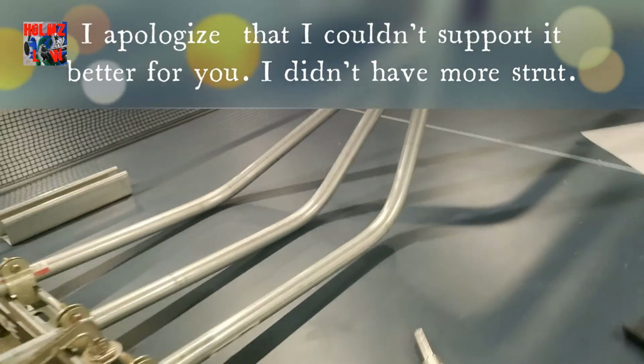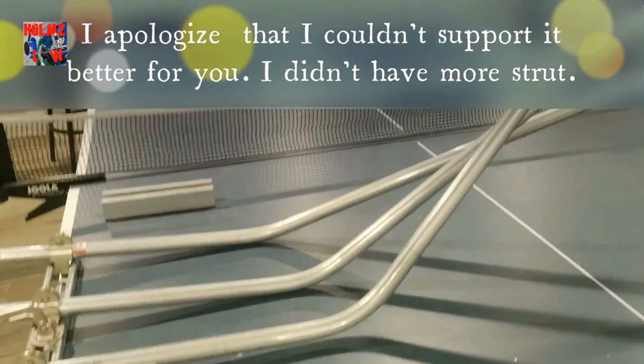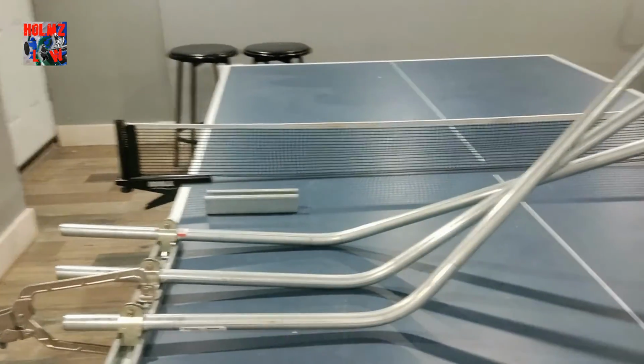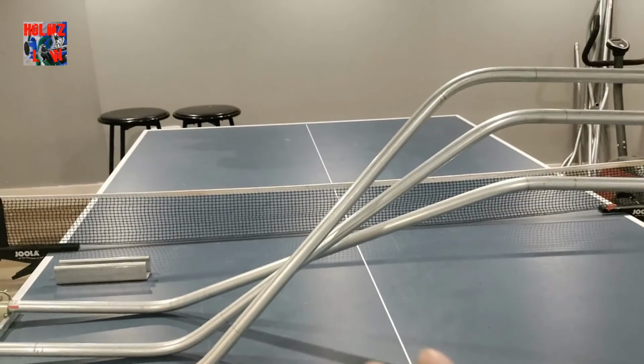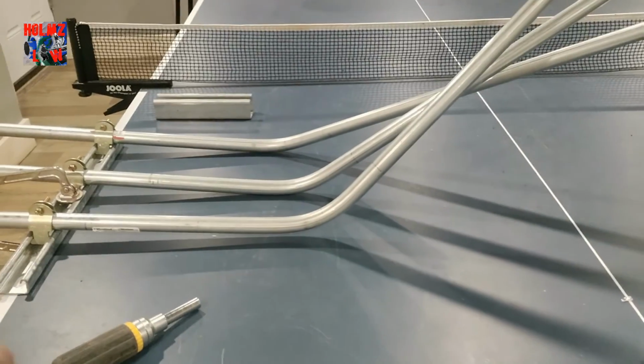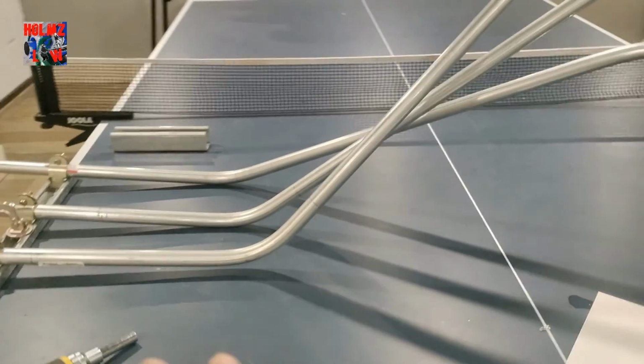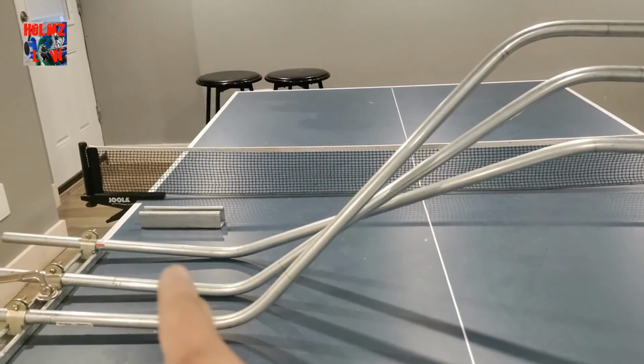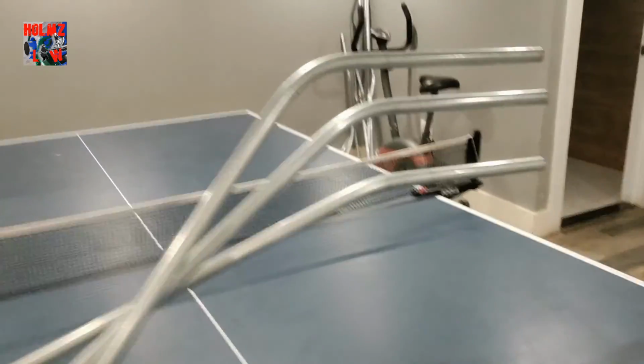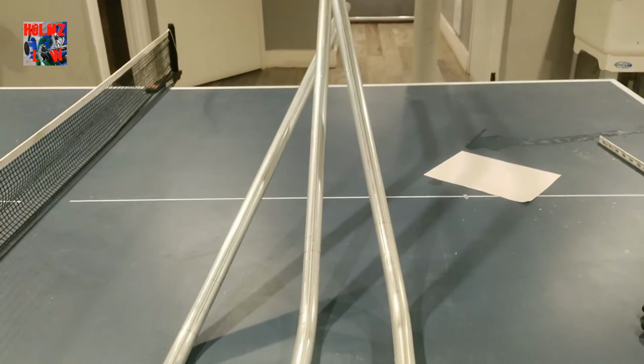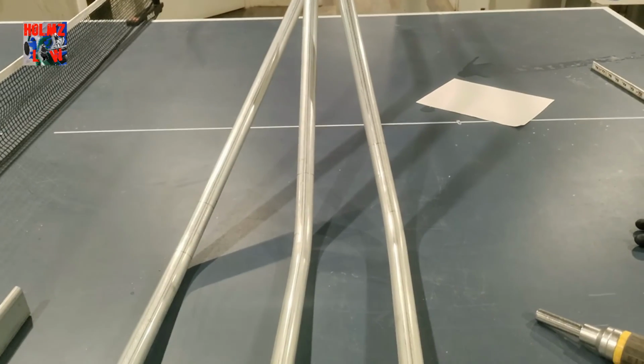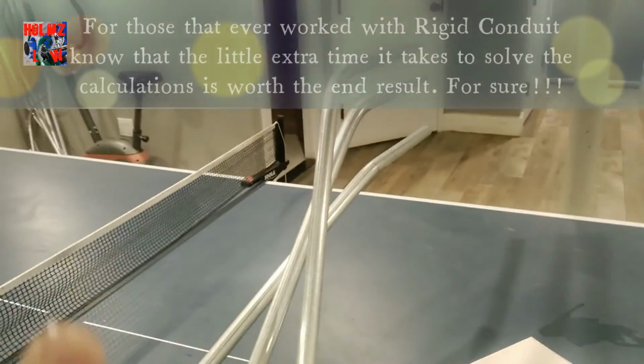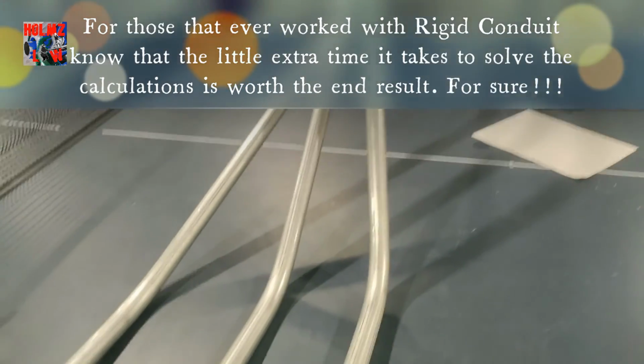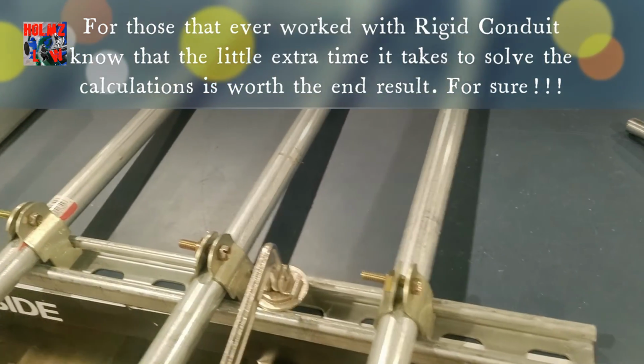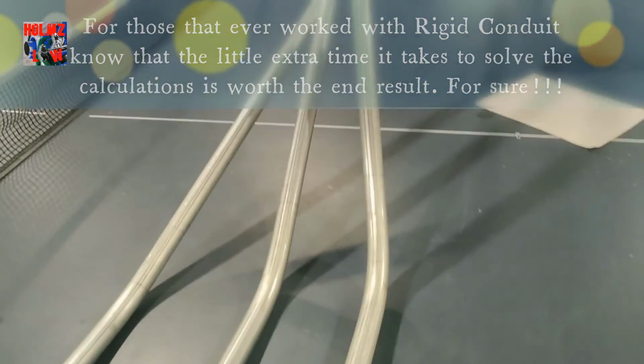Okay guys, so this is the end result. It's not the best, but it's what I can actually do now. They're all spaced out at 6 inches. They're not perfect, as you can see, because of how I'm holding it. I've got a clamp, and I didn't have a long enough strut to put on the other side, but this is the true parallel rolling offset. You're not going to have 6-inch spacing on 3/4 pipe out in the field, but this is the actual true parallel rolling offset. I apologize for the setup, but this is all I had. I'm not at the job.